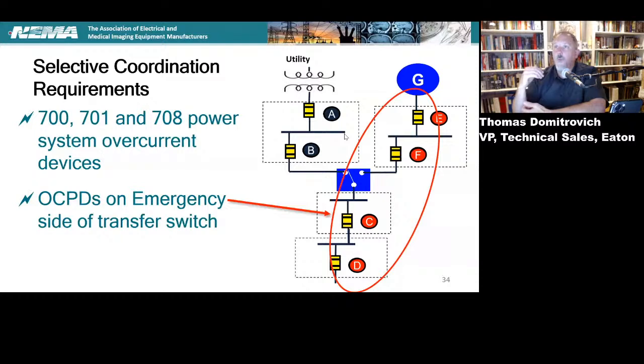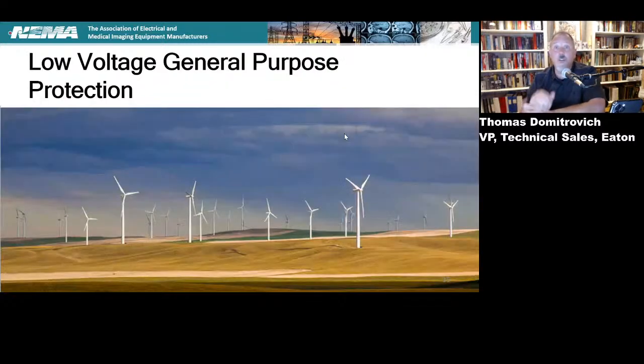And from what Massachusetts has done by pushing to 0.1 seconds, the design engineer will probably meet the 0.1 seconds and ignore fault current in the design. I know that's how I will quote a job in Massachusetts. And that's how I quote jobs in other areas that are enforcing 0.1 seconds, especially in healthcare. But for the life safety system, that's a challenge because healthcare has all of these other redundant provisions in making a hospital. You've got big generators in there. You've got isolated power supplies. You've got all of these other things, which is a part of the argument on why they're giving some of that forgiveness. But in an Article 700, 701, and 708 system, that's a lot of cookies to be putting into 0.1 seconds.